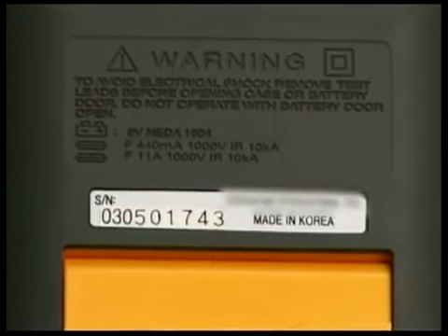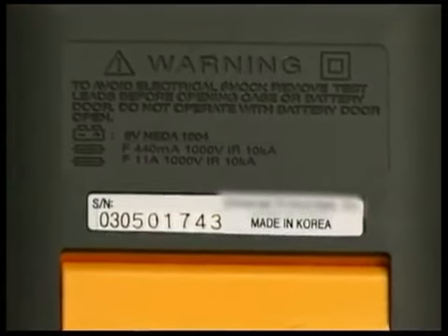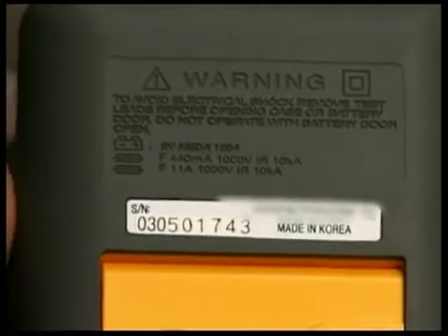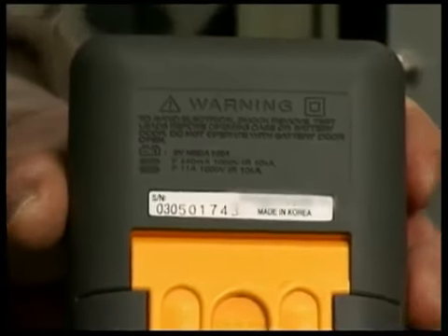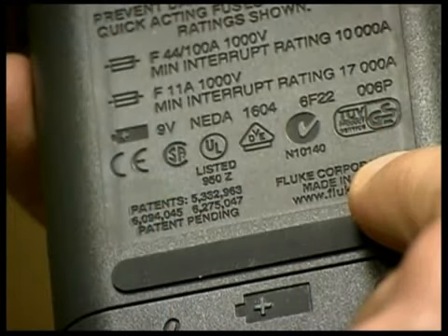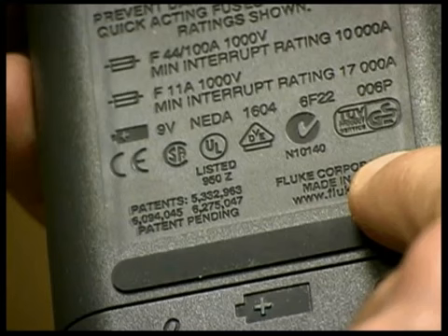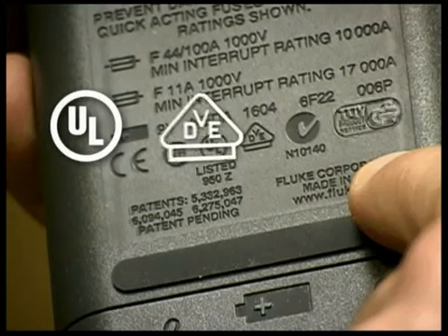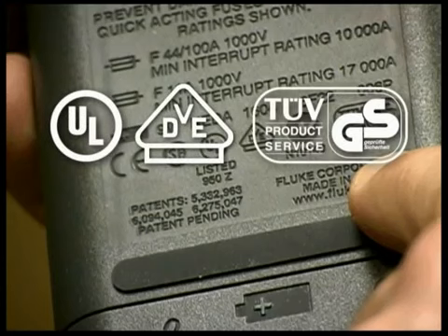How could this meter fail? The standards bodies only create the standards. They do not enforce them. A meter that claims to be designed to a standard may have never been tested. That's why it's essential that your tester is certified by 2 or more independent testing laboratories, such as UL in the United States and VDE and TUV in Europe. This is the only way you can be sure your testers have passed the most rigorous tests and meet every applicable standard.